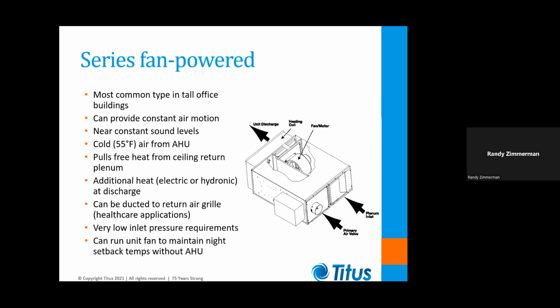Usually filters are used to protect the motor and blower from dust contamination during construction, but usually during the balancing and commissioning phase, that filter is thrown away. But also I should say that if that blower were running backwards, it would still be moving about 50% of the rated airflow to the room. It's not going to blow the filter off. If the filter's being blown off, it's because you have excess primary air dumping out through the induction port.